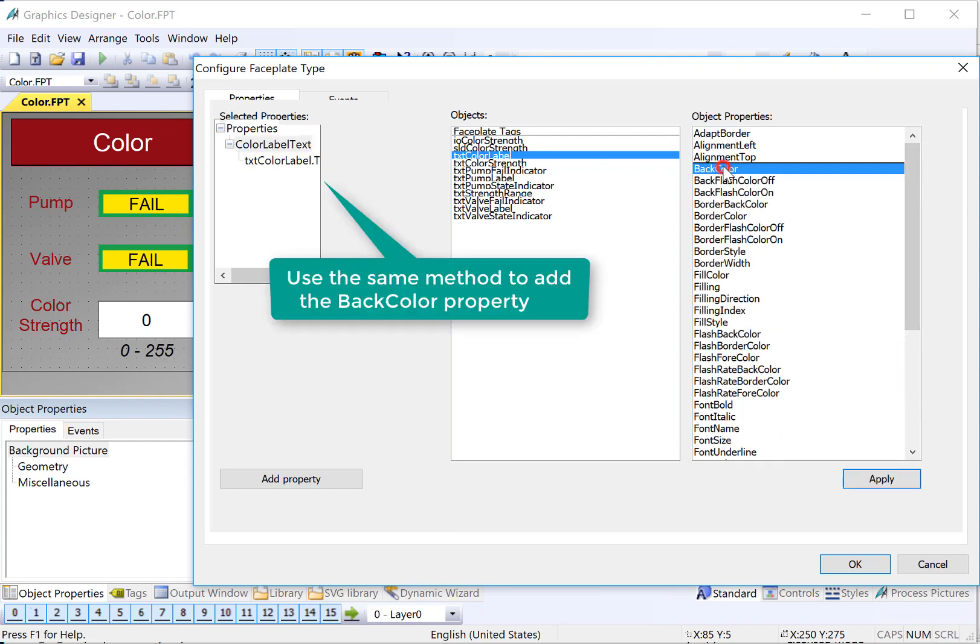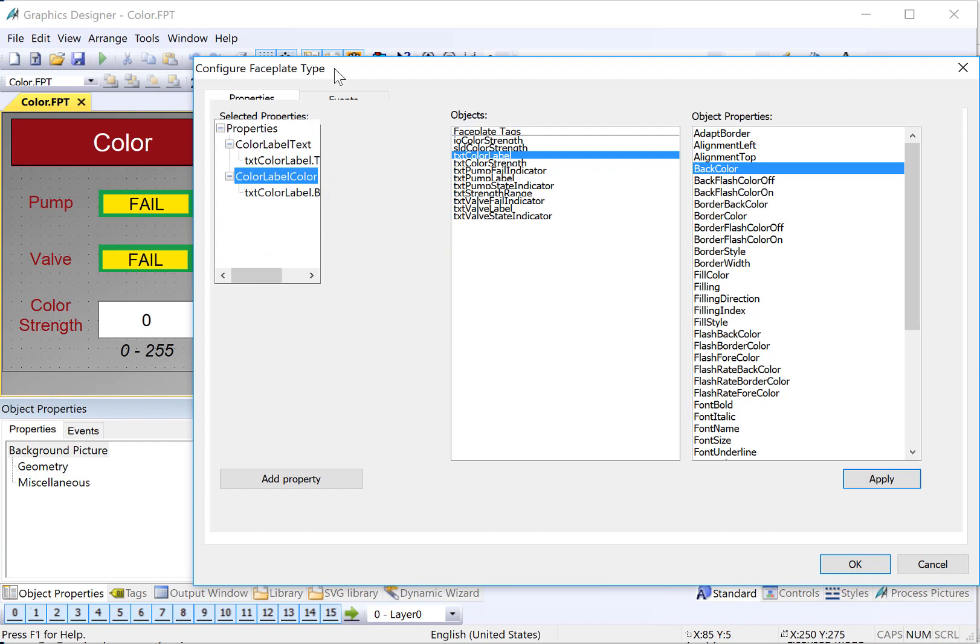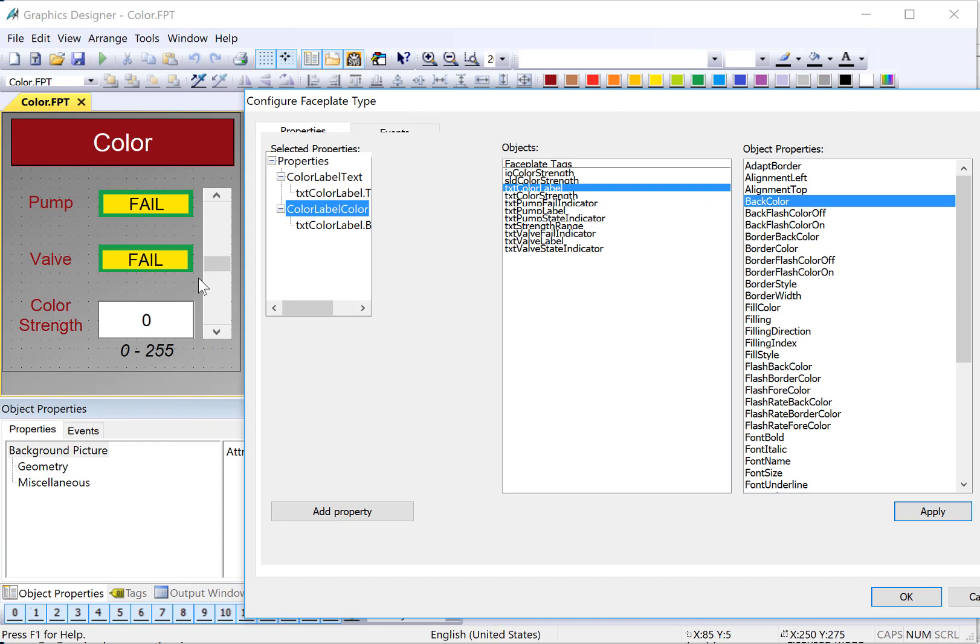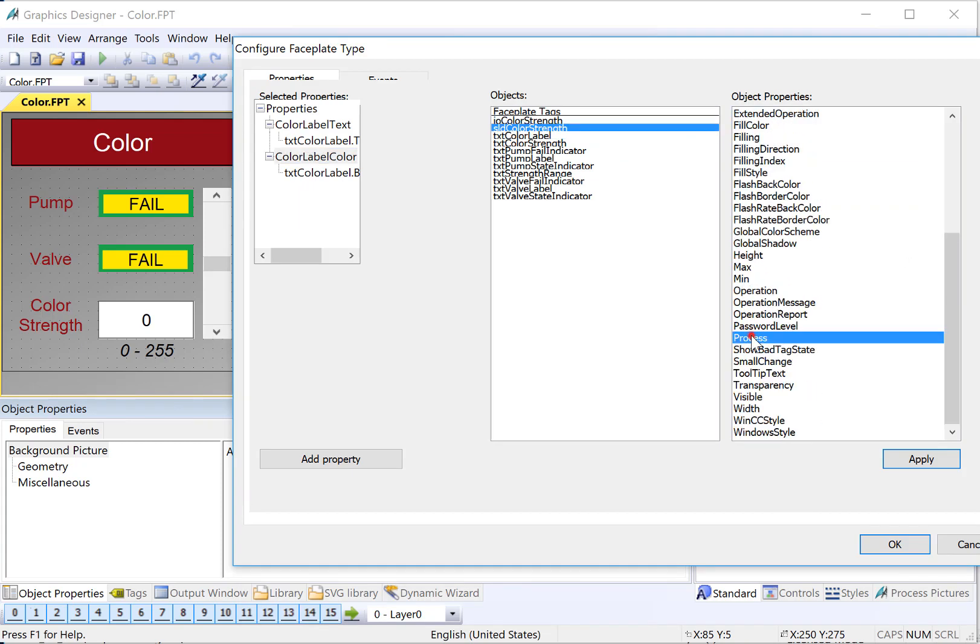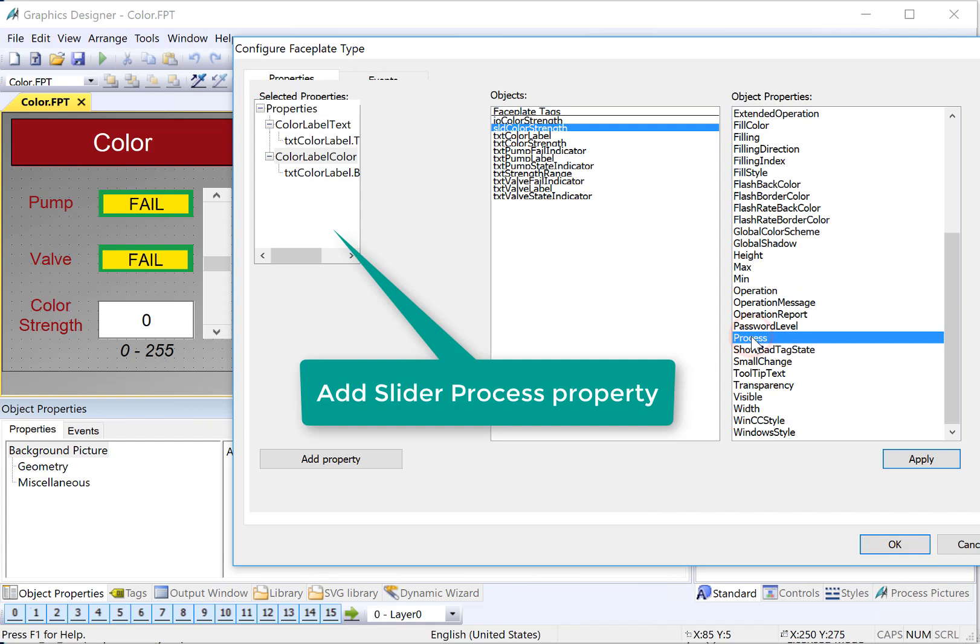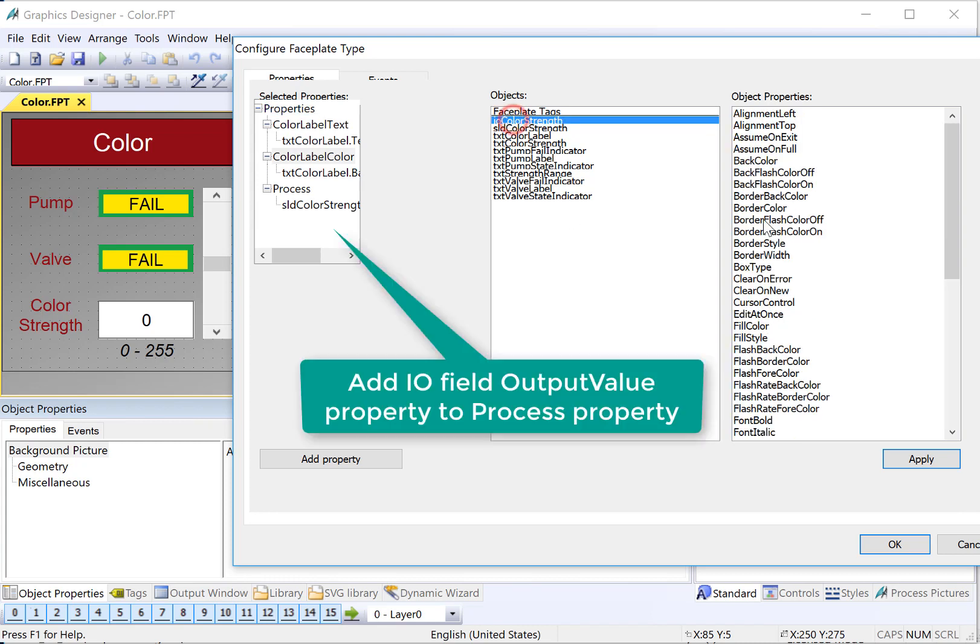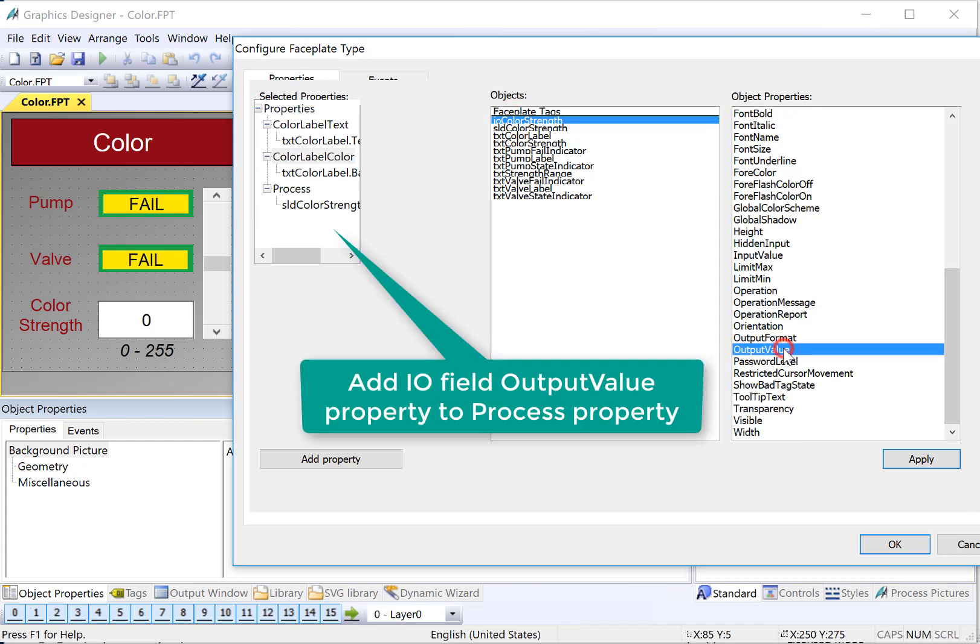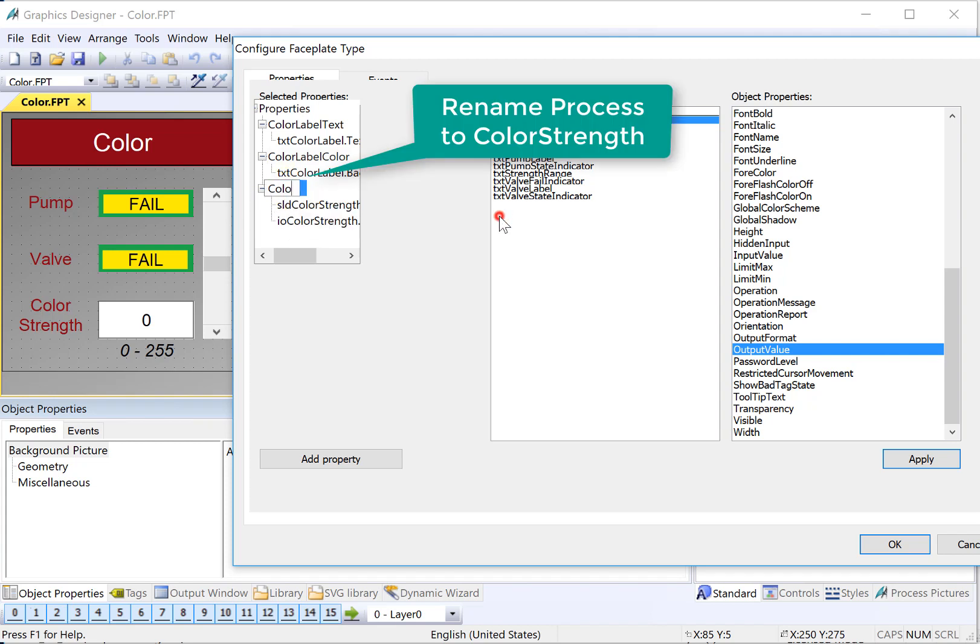Next, we want to add our color strength value, which would go to both our IO field and our slider. So first, I will find the slider and the property that defines the value of the slider is called process. So I will drop it here. And then we will also find our IO field and it's the output value that defines what value is shown. And notice we're going to put it in the same place. So this number here is represented both by the slider as well as by the IO field so that we put them under the same place. We'll go ahead and give this a name, color strength.